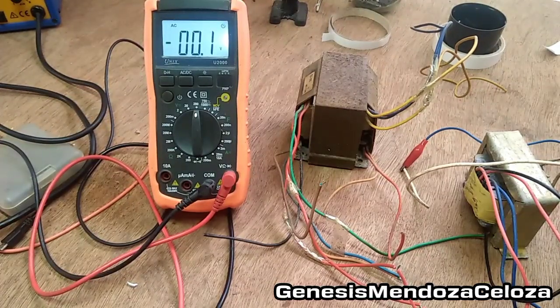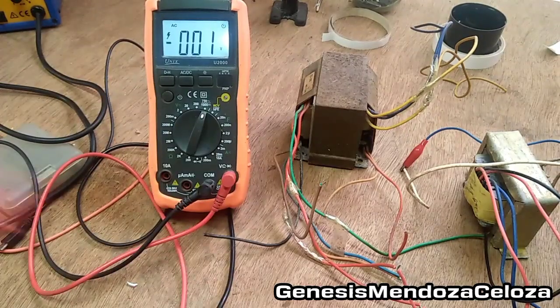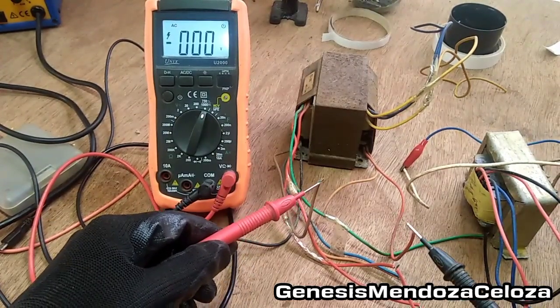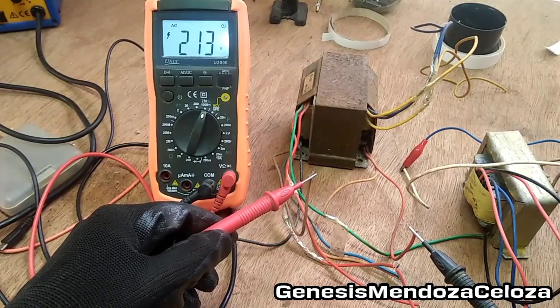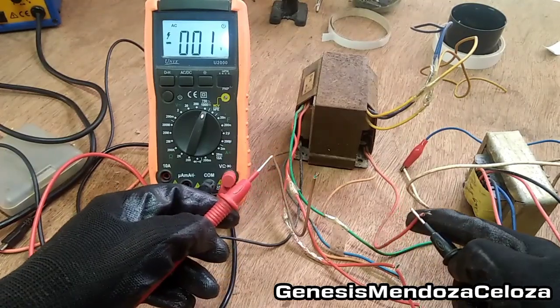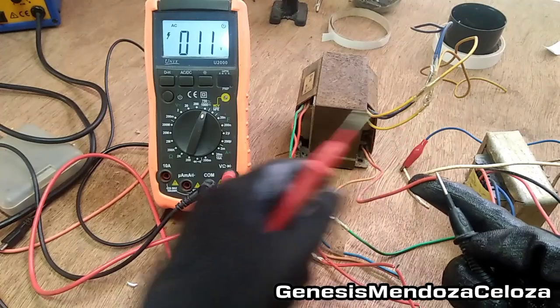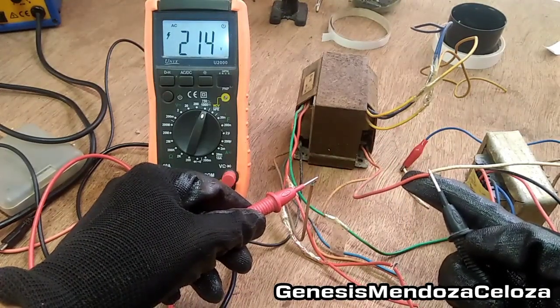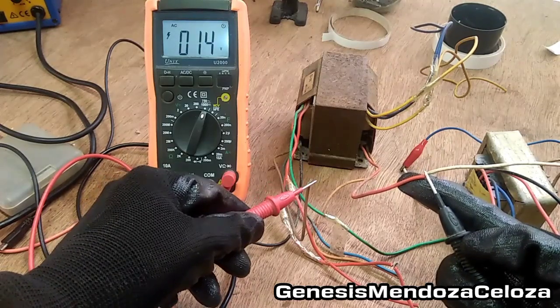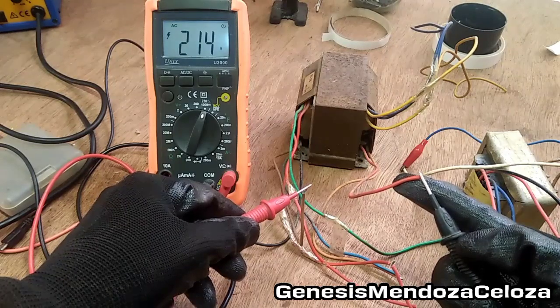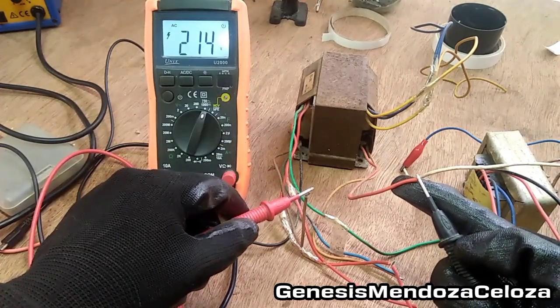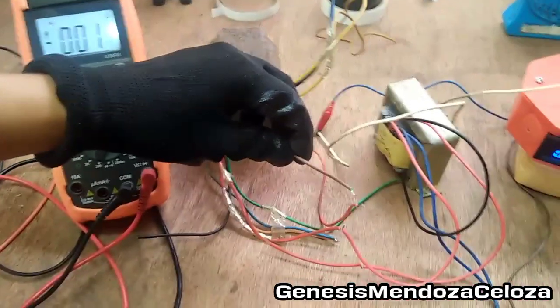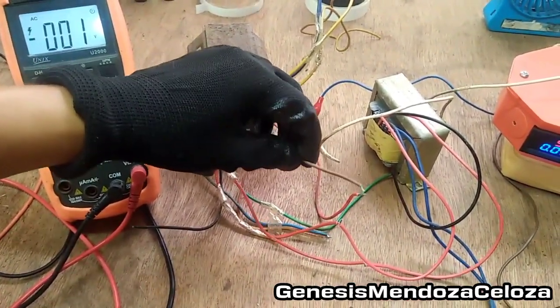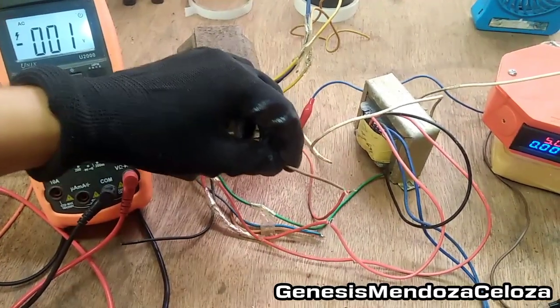Not all definitions of the term isolation transformer are created equal. For some purposes, this may mean just preventing line-borne electrical noise from passing to the equipment. So, if you acquire something called an isolation transformer, on its nameplate, confirm that the primary and secondary are indeed not tied together by a low resistance. If they are, it can probably be modified for service needs by disconnecting a jumper, but it may not have the insulation ratings desirable for high voltage isolation.